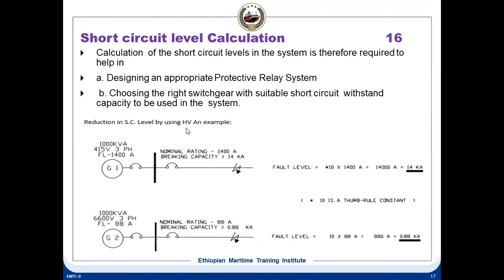Here, this is another advantage of high voltage: by stepping up the voltage, we are reducing the current, and that has a direct effect on the short circuit level calculations. Because you can see here, this is a 1000 kVA 415 volt three-phase generator. It's producing 415 volt, or let's say 440 volt, three-phase. The full load current is 1400 amps. This generator is producing 1400 amps.